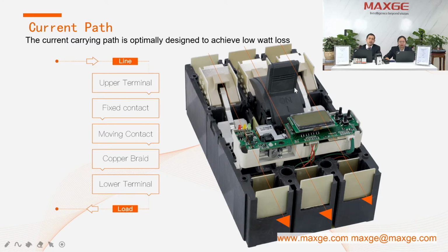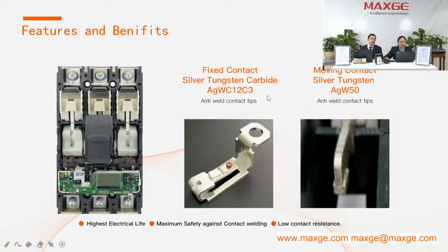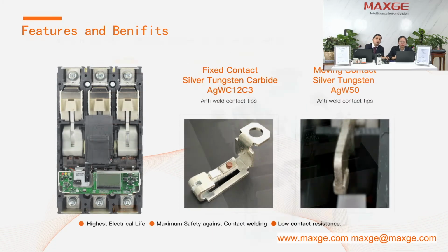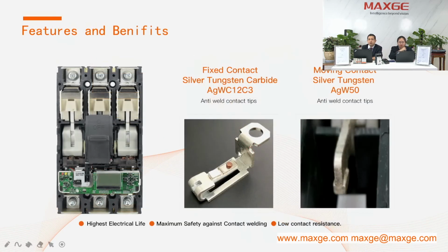This is the current path of the MCCB. In this slide you can see we use a U type fixed contact, and we use silver buttons. Here is the silver button on the fixed contact, and here the silver button on the moving contact. The silver button on the fixed contact is AgW C12 C3, and on the moving contact we use AgW 50. The advantage of this combination is high breaking capacity and high electrical endurance, and the MCCB can easily pass the tests with this combination. So you must check which type of contact buttons the competitor's MCCB is using. This combination is the best combination.